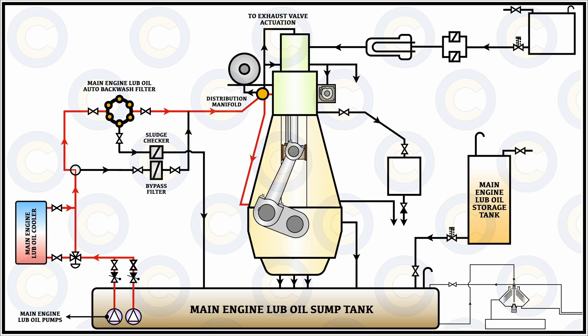Once this oil passes through the common manifold, it has to go to lubricate the crosshead. The oil when it reaches the crosshead will lubricate the lower end — that is the crosshead bearing shell — and then travel up. A certain amount of oil will also pass through the piston rod into the piston side. This oil does two different jobs: cooling of the piston and removal of heat gained during the combustion process, and also lubricating the different moving parts within this system.